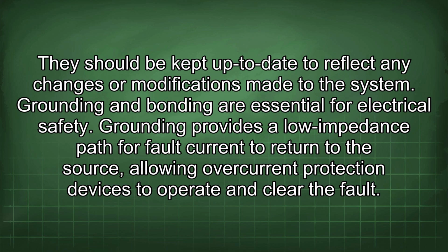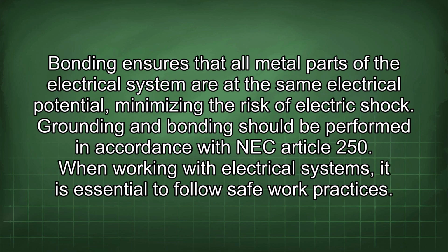Grounding and bonding are essential for electrical safety. Grounding provides a low impedance path for fault current to return to the source, allowing overcurrent protection devices to operate and clear the faults. Bonding ensures that all metal parts of the electrical system are at the same electrical potential, minimizing the risk of electric shock. Grounding and bonding should be performed in accordance with NEC Article 250.